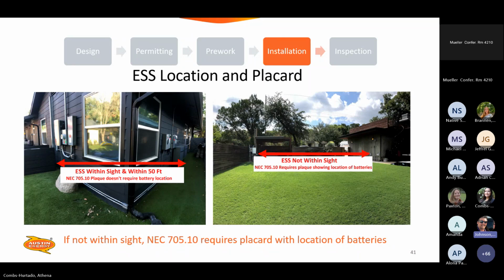And the placard does need to be rated for the weather. It does need to be UV resistant. I did see a sticker yesterday that's probably only been on there for a month, but it's already peeling itself and it's bubbling itself up. So that one does not meet the design criteria for placards for ESS location.